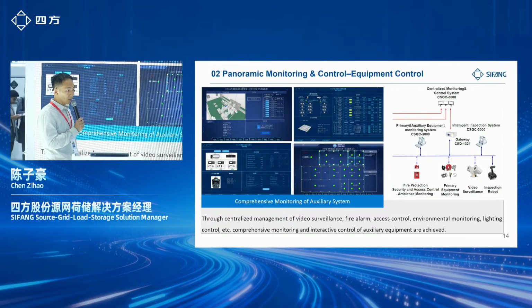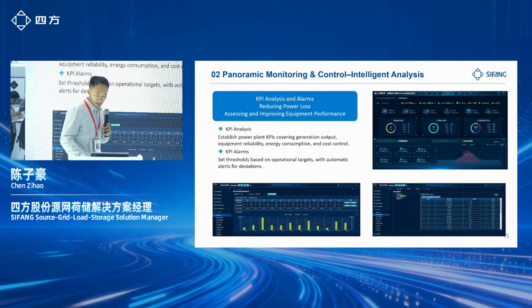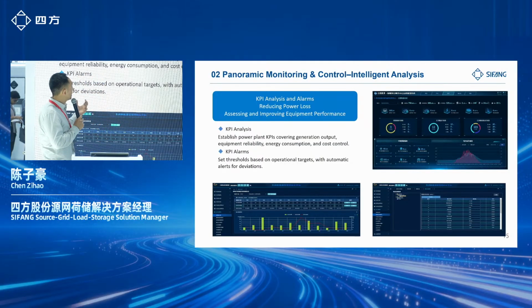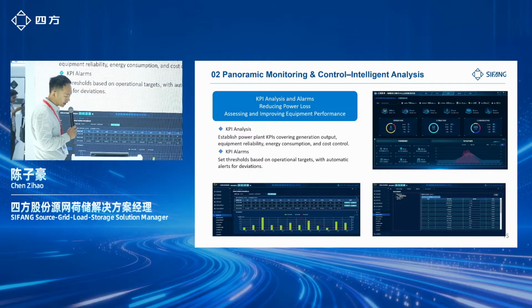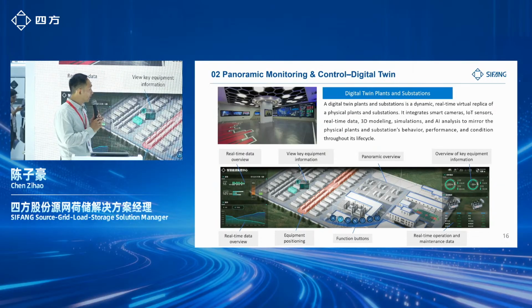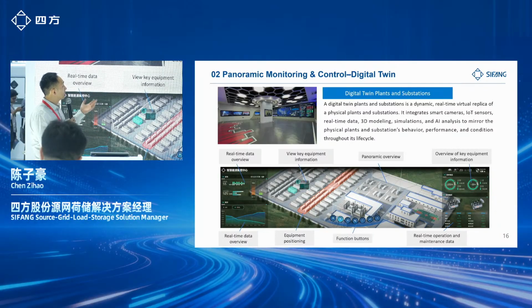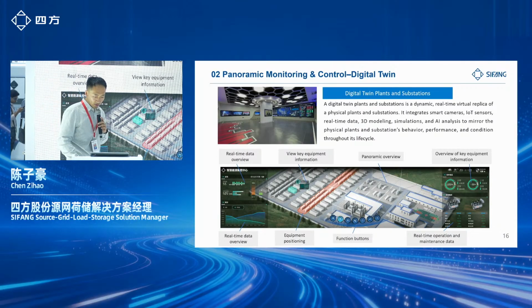And also for the auxiliary system, we can support this CCTV, fire alarm system, also the environmental controlling system. To make sure the performance of the whole plant, we have this KPI analysis and alarms, reducing power losses, and establish the different ways to analyze the whole plant. We can look at the generation output, the equipment reliability, also the energy consumption. In some cases, we also provide this digital twin for the whole system. Digital twin plants and substation is a dynamic, real-time replica for the physical plants. It integrates the smart cameras, IoT sensors, also the real-time data, and improves the efficiency of the maintenance.